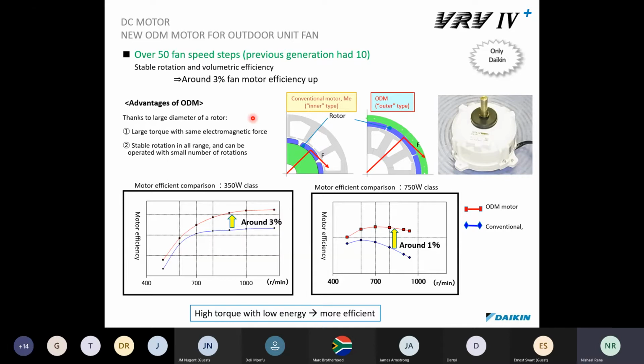So the advantages of the ODM is that you obviously have a large torque with the same electromagnetic force, right? Looking at the conventional motor, with the inner part, to the ODM with the outer part, there's over 50 fan steps, and the previous generation had 10. So what does that mean? Because you've got more steps, you've got a more stable rotation, and you have better volumetric efficiency.